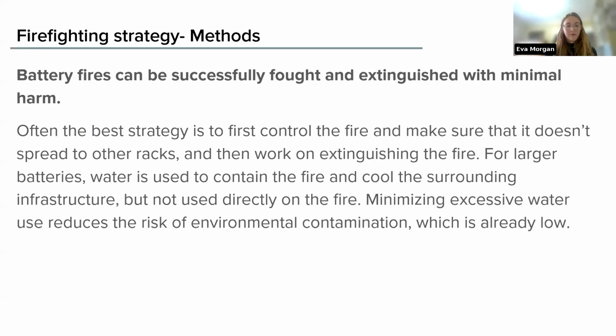Battery fires can and have been successfully fought and extinguished with minimal harm. Water is still considered the best cooling agent for battery fires under NFPA 855. There are other cooling agents being tested, but water is still most widely recommended. The best strategy is often to first control the fire, then extinguish it. For larger battery installations, water is used to contain the fire and cool surrounding infrastructure, but isn't directly used on the fire. Minimizing the use of water is important in reducing the risk of environmental contamination, and that risk is already very, very low.